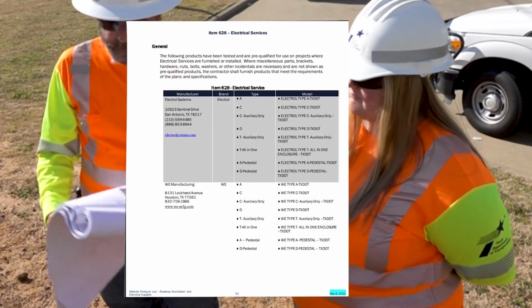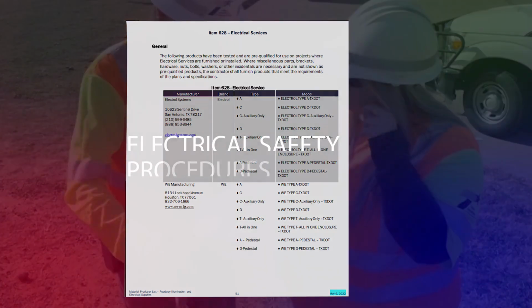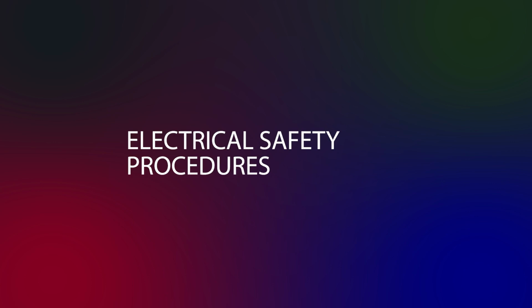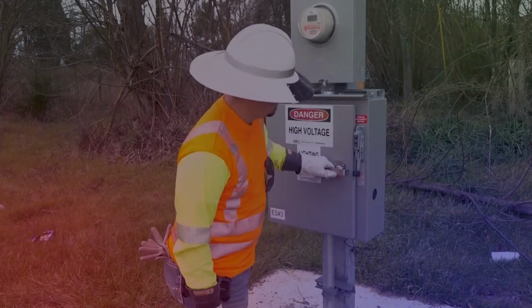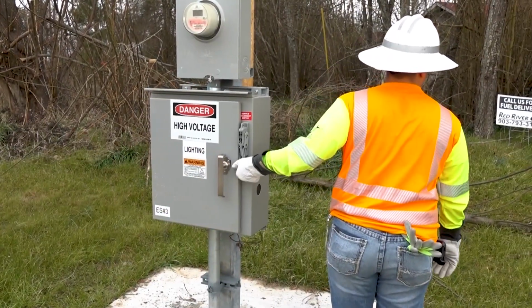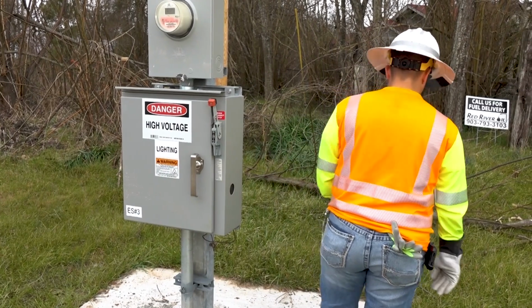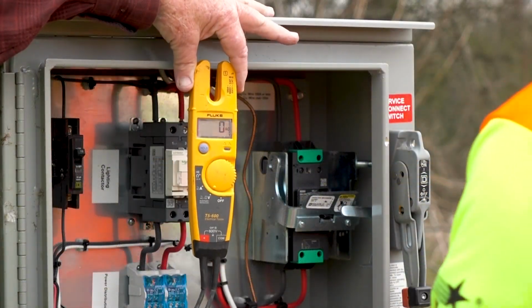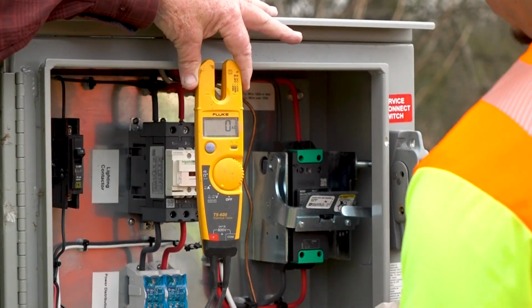The installing contractor must provide a Type A service from one of the manufacturers shown on the MPL. When inspecting any electrical equipment, all safety procedures must be followed. As the absence or presence of electricity cannot be determined by human senses alone, it is necessary to use a known good voltmeter to confirm that power is off.